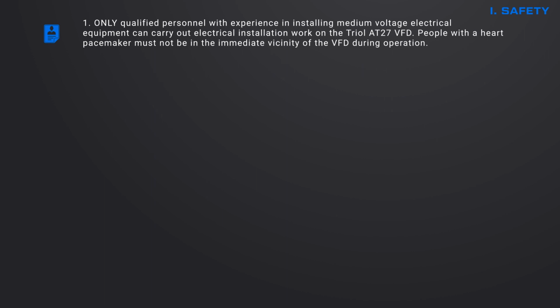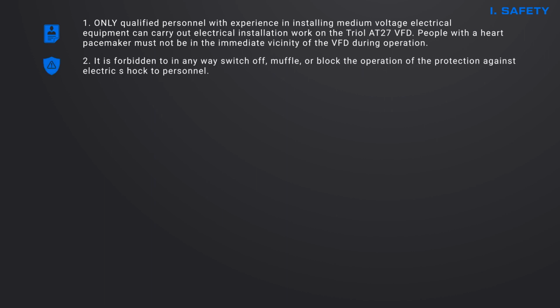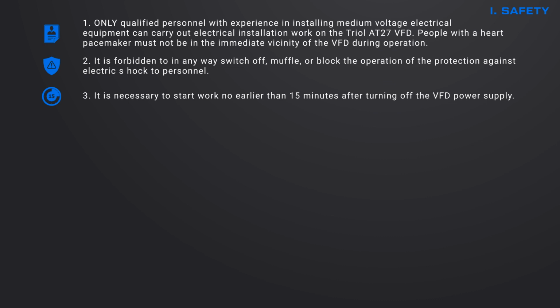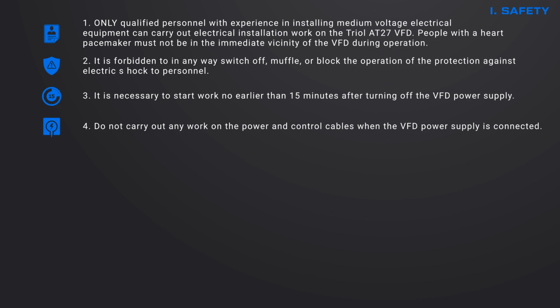Ensure that unauthorized personnel cannot access the VFD. People with a heart pacemaker must not be in the immediate vicinity of the VFD during operation. When setting up and operating the VFD, it is forbidden to in any way switch off, muffle, or block the operation of the protection against electric shock to personnel. After switching off the VFD power supply, dangerous voltages may remain on the live parts. In order to avoid electric shock, it is necessary to start work no earlier than 15 minutes after turning off the VFD power supply. Do not carry out any work on the power and control cables when the VFD power supply is connected. Hazardous voltages from external sources may also be present at the relay outputs, even if no supply voltage is applied to the input terminals of the VFD.